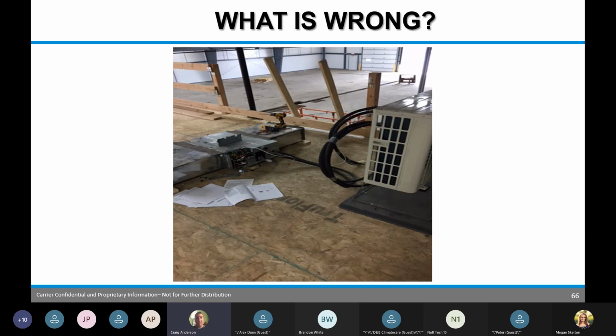This is a ducted unit. The manual is out, but I think the manual came out after the fact because they had an issue with it. If you're not sure of what you're installing, open the manual. This one here, there were 11 units. These ducted units have brackets on them to put threaded rod through to hang them from a ceiling. They thought the brackets were to screw it to the ground. They installed all these units upside down, all 11 of them. They turned all 11 on. They all coded out because the float switch inside was upside down. So be mindful. Open the manual if you're not 100% sure, just to see what you're installing. They had to go back and reclaim all of them, flip the units upright, and get them up and going.